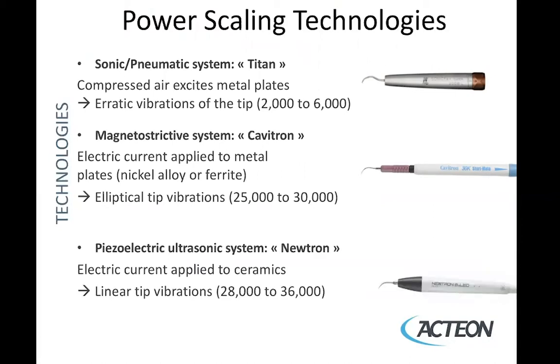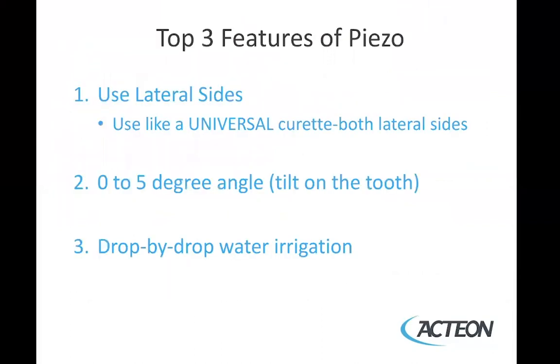Piezoelectric is another type of ultrasonic, and an example is the Newtron, which you have at your school. In that situation, an electric current is applied to the ceramic discs in the handle, creating linear tip motion at 28,000 to 36,000 cycles per second.